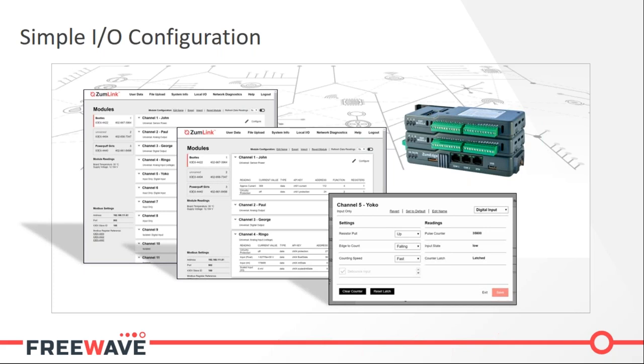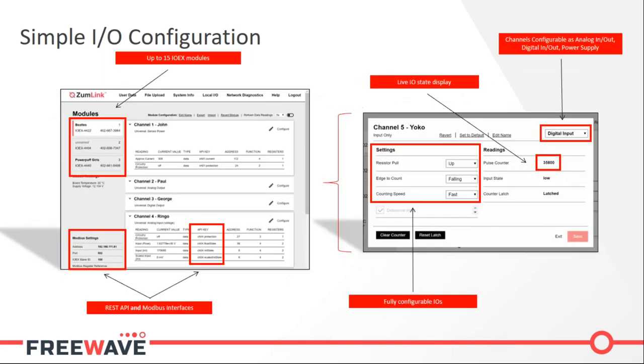Configuration, adding and changing sensors, as well as reading and writing, can all be done with that same tool on the device itself — no programming required. From this single configuration page the user can configure up to 15 IO EX modules with up to 12 channels each. Each IO point can be fully characterized with details like pull-ups and pull-downs, output voltage, input range, and counting on rising or falling edge. All interface reference information for the IOs is included on the configuration tool, so no looking up Modbus information from a reference manual.